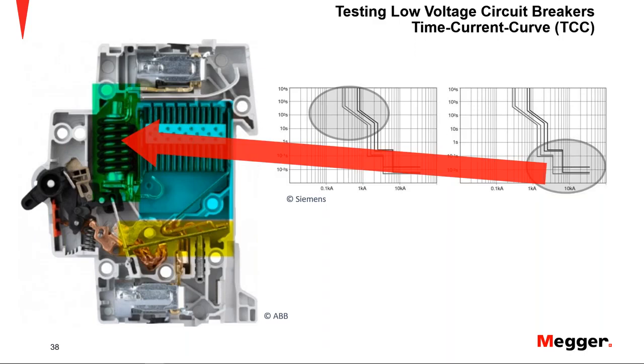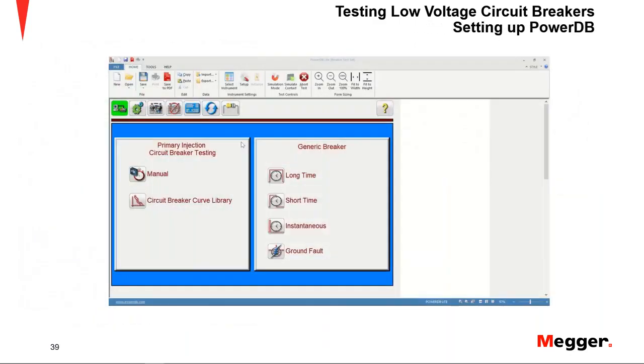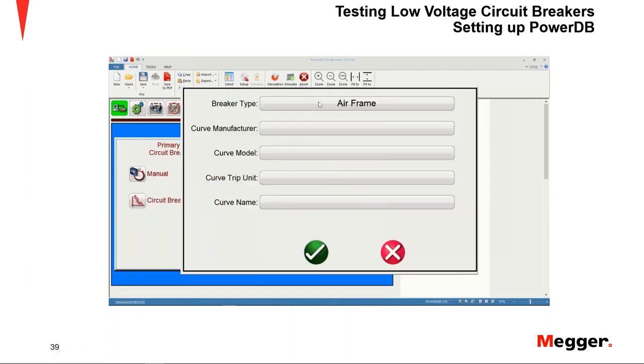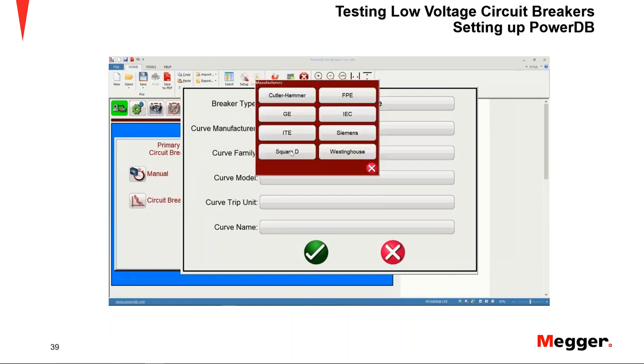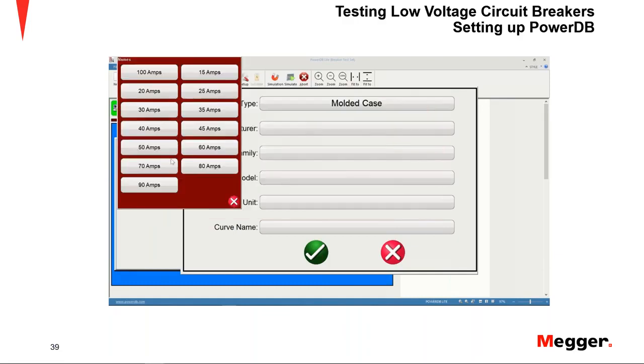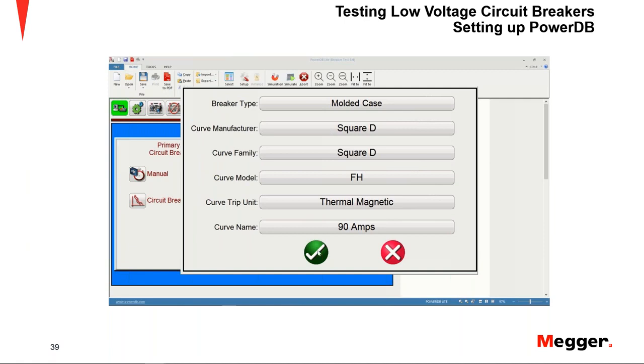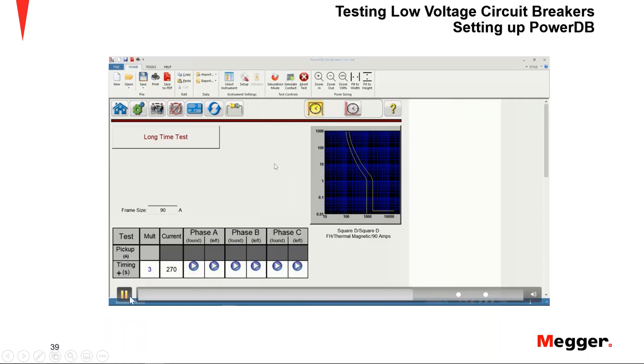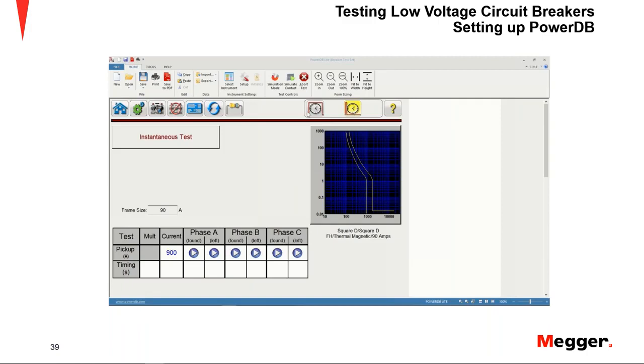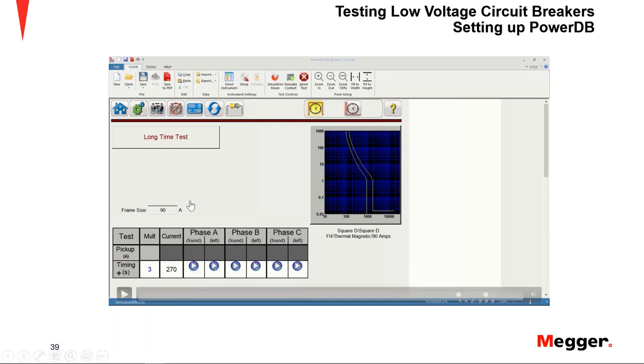And so now, assuming we have our connections made to the first pole of the breaker, first we need to set up PowerDB. And again, as I mentioned before, there is a circuit breaker library, so we need to select the breaker we are going to test. So we're going to click on circuit breaker curve library, say manufacturer specific, and choose between molded case and airframe. I tell the software the manufacturer. I'm going to use a Square D as an example from the FH family, rating of 90 amps. Accept my selection, and the software will show me the curve. I can see that I have both long time and instantaneous testing, so no short time for this breaker. Notice also the frame size is already indicated, because I selected the breaker from my library.